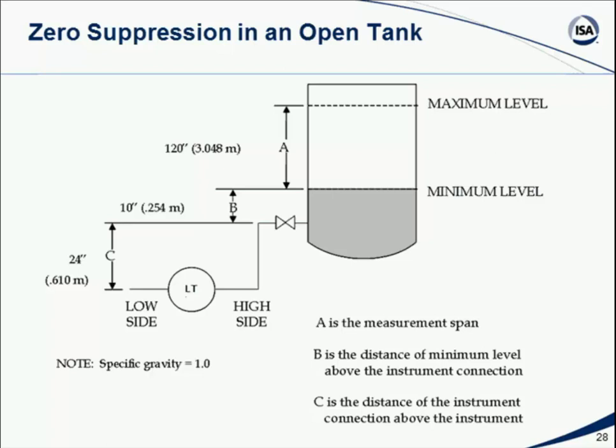So when we talk about taking a measurement, and in this case where we use a fluid-filled line, an impulse line, to leave the tank and bring the fluid over to the level transmitter itself, we've got to remember that that line, that impulse line, is also filled with fluid. And that fluid is going to press down and be providing a bit of pressure itself. So in this particular case, we've got the problem of zero suppression. We've got to correct for certainly C inches or 24 inches of fluid.